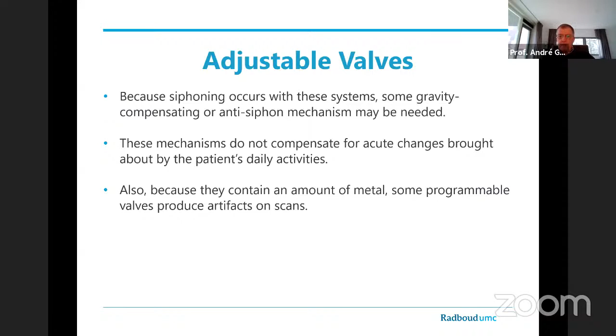And also, all these differential valves don't compensate well for acute changes: the daily activities, sporting, bending over, walking, being active, coughing. All these things are not well adjusted. Valves can't react to that. They just see that there is a difference between proximal and distal. And therefore, they are still prone to overdrainage.